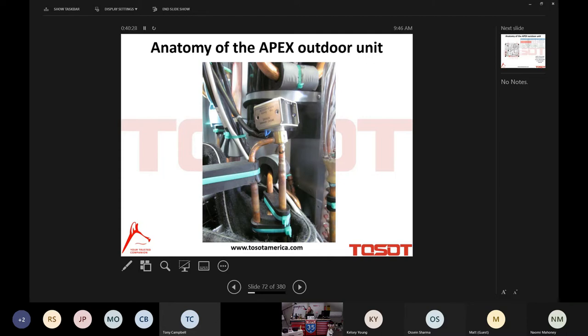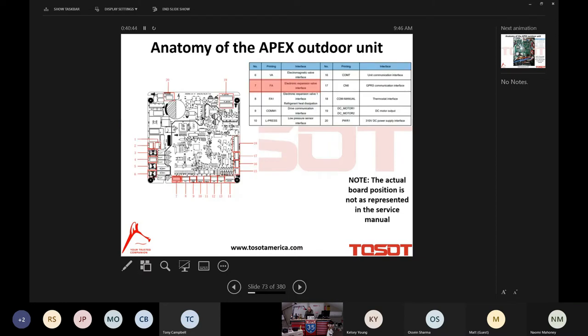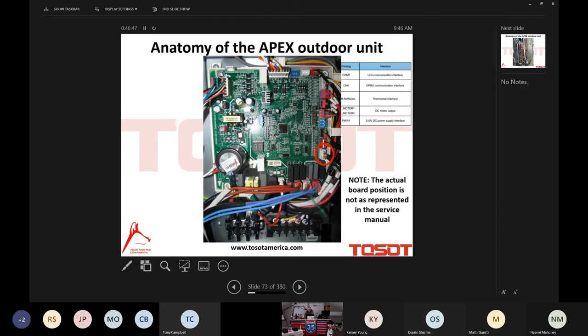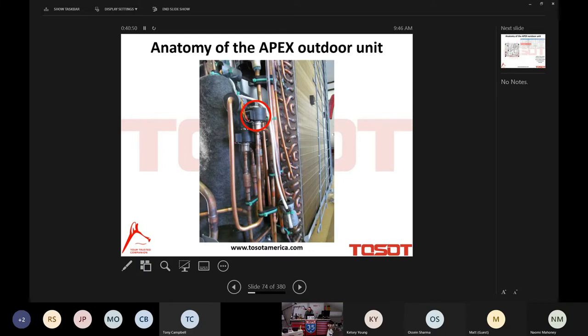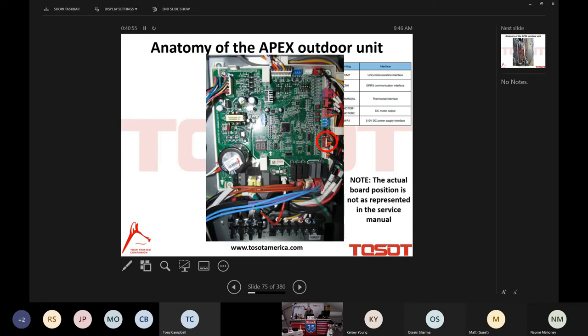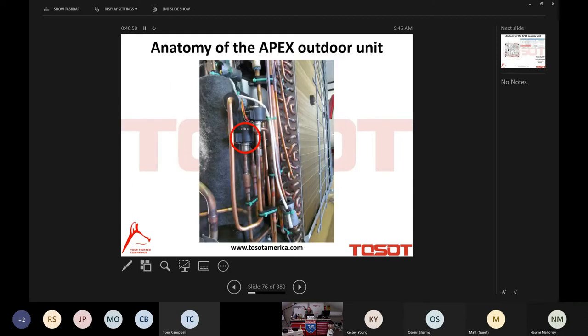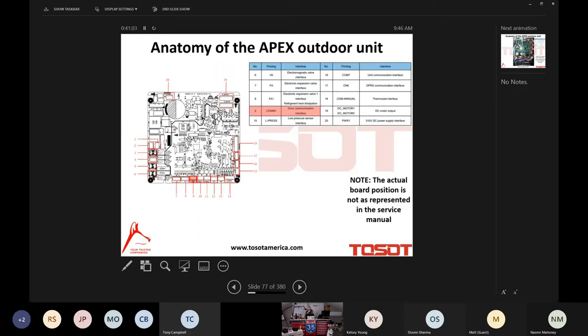You know, electromagnetic valve is just a fancy way of Tosot to say that that is a bypass valve. When it's energized, we're allowing the EEVs of the indoor unit to do their work. When it's not, the TXV of the indoor unit is doing its work. And mentioning the EEVs, the electronic expansion valves, here they are of the Apex outdoor unit. Here's number one, and just about right next to it is number two. And again, they're doing the work in the heating mode, the TXV of the indoor during the cooling mode.